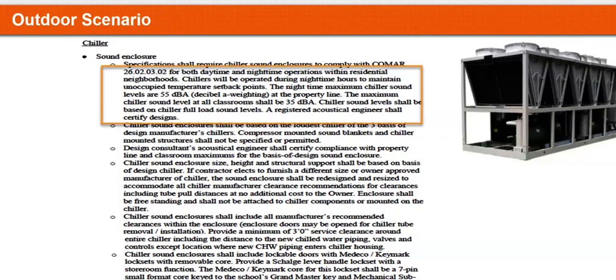In front of you, you have a typical specification that's becoming more common, especially when you're close to schools. In this case, you'll see that the nighttime maximum sound level is 55 dBA close to residential. And at the school, because this was right on a schoolyard, it's 35 dBA. So you have a unit that's at 90 decibels to get it to 35. You're going to need a big enclosure for that. Additional to that, you have to account for spacing. You cannot put anything in front of these units.